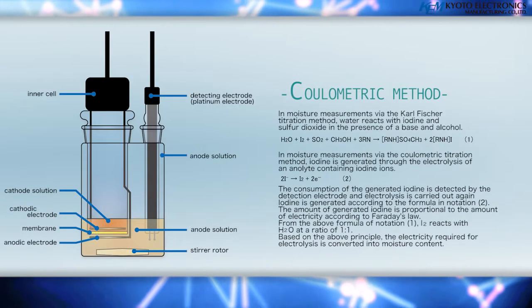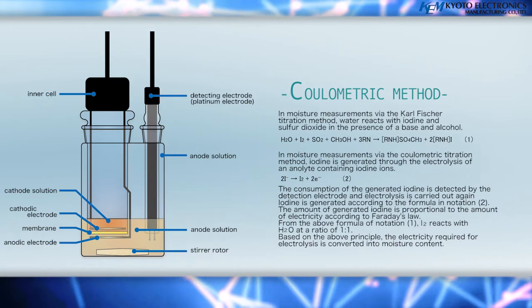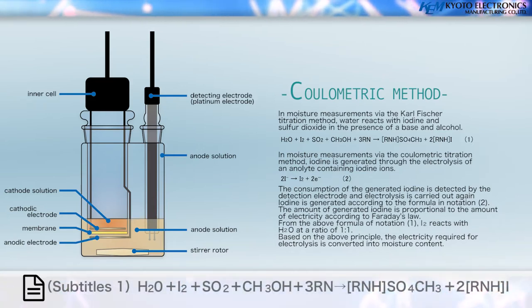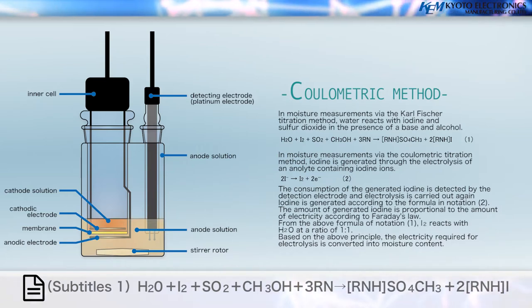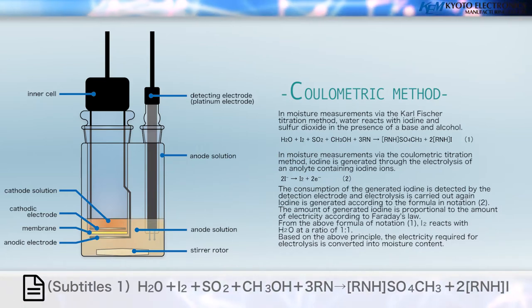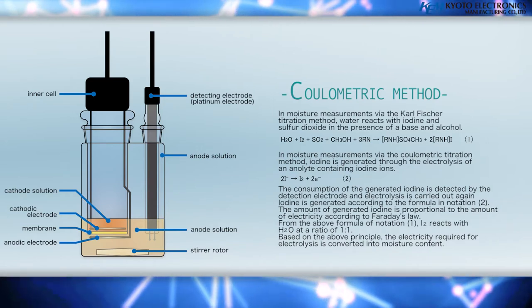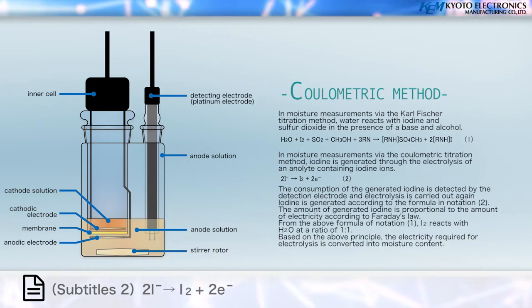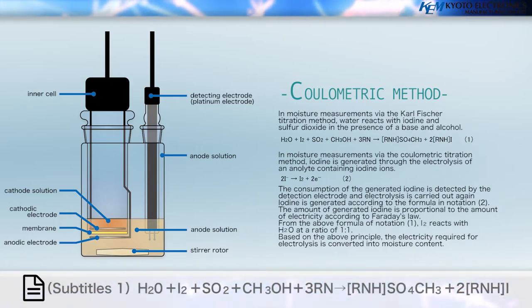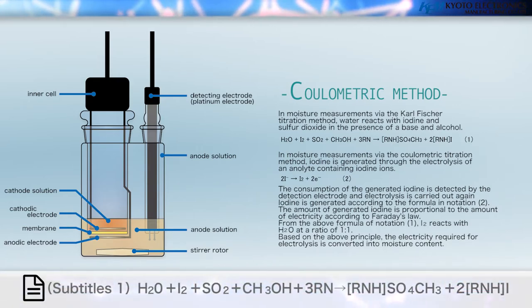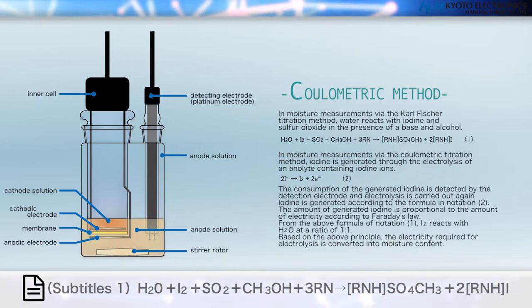In moisture measurements via the Coulometric Titration Method, iodine is generated through the electrolysis of an analyte containing iodine ions. The consumption of the generated iodine is detected by the detection electrode, and electrolysis is carried out again. Iodine is generated according to Faraday's law, where the amount of generated iodine is proportional to the amount of electricity. From this, I2 reacts with H2O at a ratio of 1 to 1, and the electricity required for electrolysis is converted into moisture content.